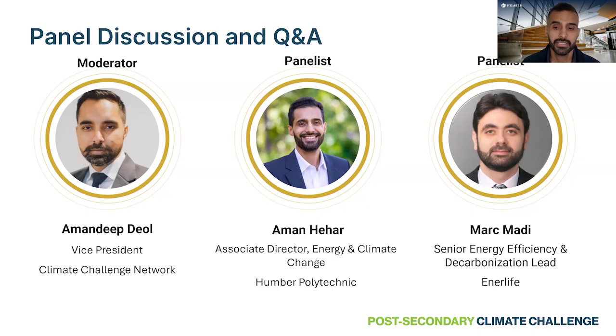Another big win for us at Humber has been integrating our lighting occupancy sensors into our BAS. It's around this theme of turning things off when people aren't there. Our automation system now knows when a space is unoccupied, so it closes the damper on the VAV box, goes to a setback temperature, the fans ramp down, and the plant equipment - boilers and chillers - stage down. We start to compound savings that way.